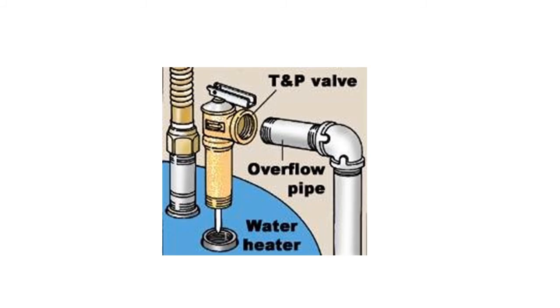The next device is a temperature and pressure relief valve, also called the TP valve. This valve protects the water heater by discharging water when the water inside the heater reaches excessively hot temperatures or high pressures. The temperature setting is typically 210 degrees Fahrenheit and the pressure setting is 150 pounds per square inch gauge. This is an excellent indicator of whether or not the water heater is functioning properly — if operating normally, there should be no water discharged from the TP valve.